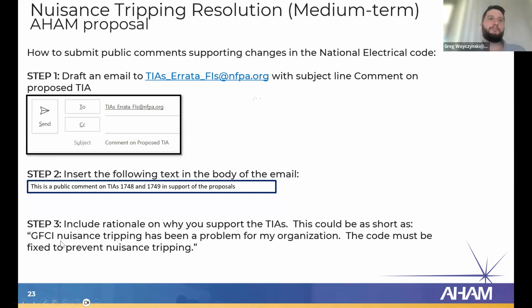And your rationale can be as simple as GFCI nuisance tripping has been a problem for my organization. The code must be fixed to prevent nuisance tripping. You can also cite cases. You know, I had a whole apartment building, a whole housing development where the washing machines didn't work, for example, or the refrigerators didn't. So this is a great way for your voice to be heard and actually get GFCIs rolled back in the electrical code. So this is one way that you can definitely help your organization avoid these cases. Of course, appliance manufacturers are going to be doing this as well, but it helps for the electrical code bodies to hear it from multiple stakeholders, not just from appliance manufacturers, but also from those boots on the ground, you all who are actually directly dealing with it. Your comments are going to have a big impact on changing electrical codes. So this is one way to do that.